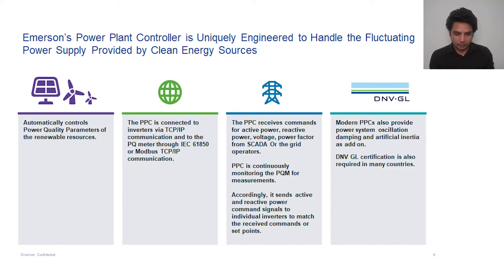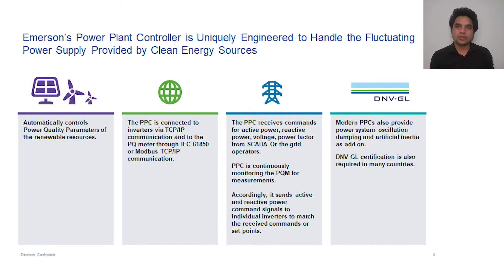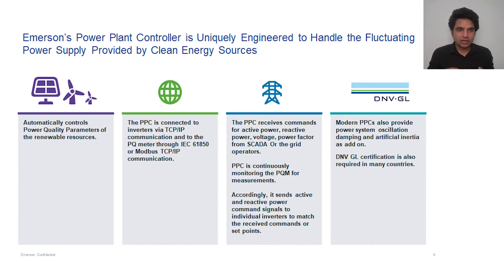How does PPC work? PPC is given a set point by the grid or by the customer. There is a power quality meter situated at the point of interconnection, which can be one kilometer or ten kilometers away. The physical connection can be fiber optic, and the communication protocol would be Modbus, IEC 61850, or any other. PPC continuously receives values from the power quality meter, looks at the set points given by the grid, and then tries to match those values by giving commands to inverters.